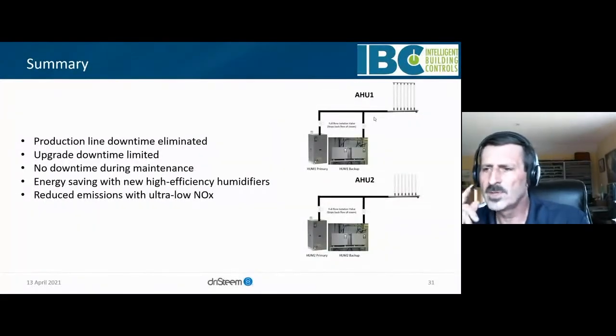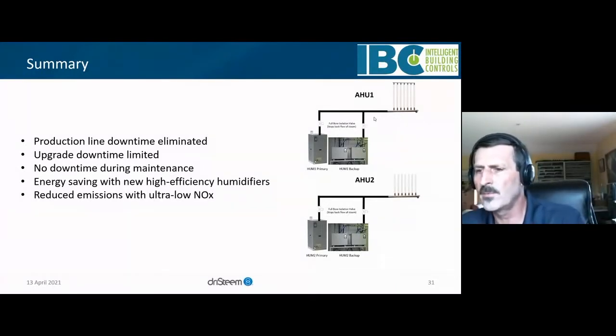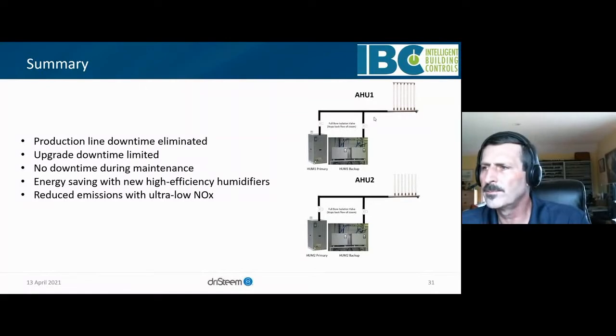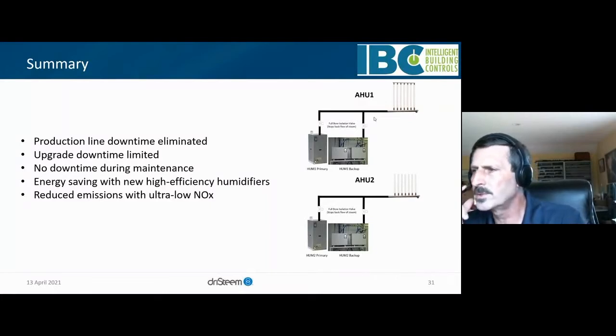The final design was an LX and HT unit on skids for each AHU. We provided full bore isolation valves as the customer had a worry about steam backflowing onto the humidifiers that weren't active. This upgrade program allowed the reuse of their RapidSorb that were already installed in the AHUs. There was no need to go through that exercise. And now they have a system that can provide steam, whether they're in maintenance mode or not.